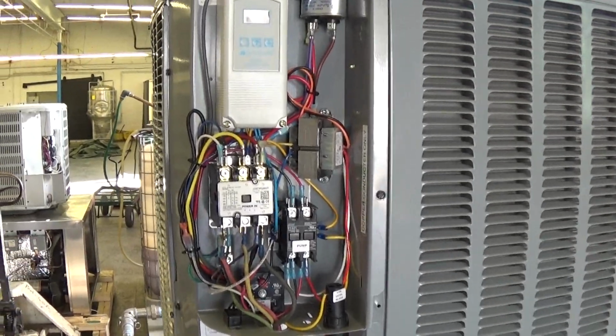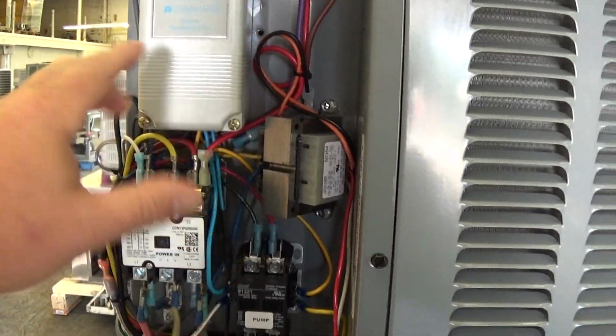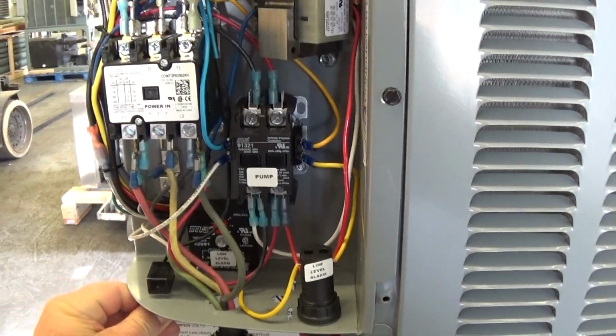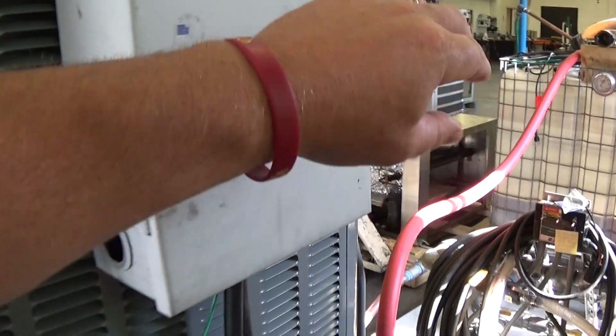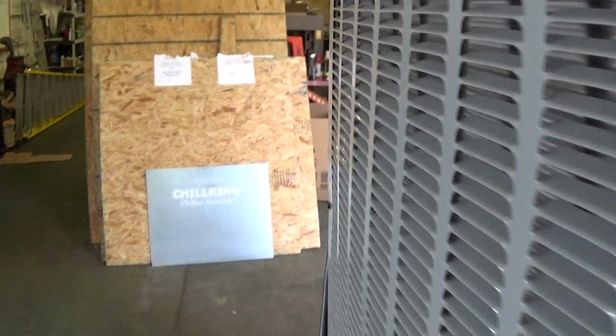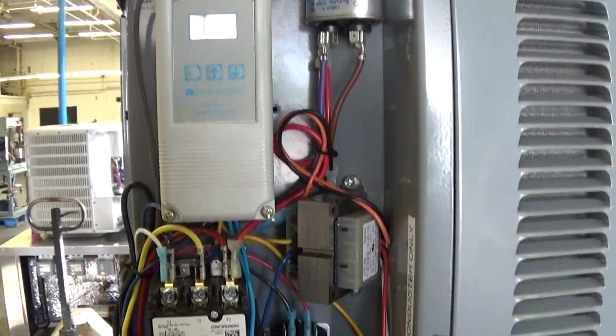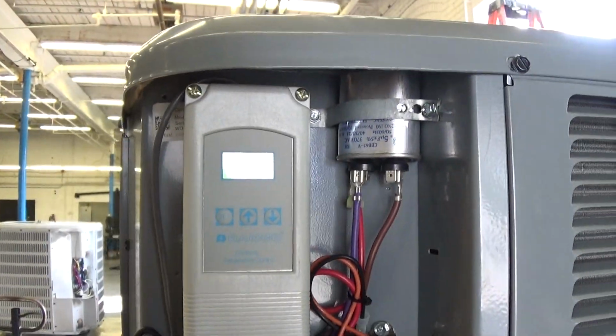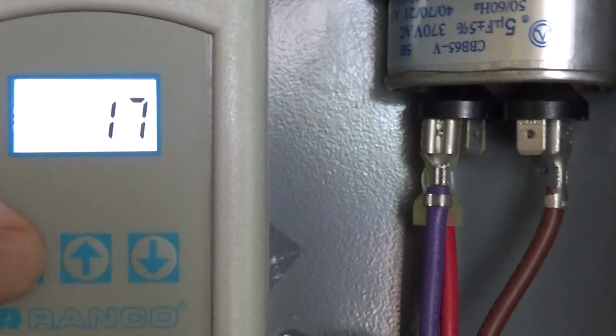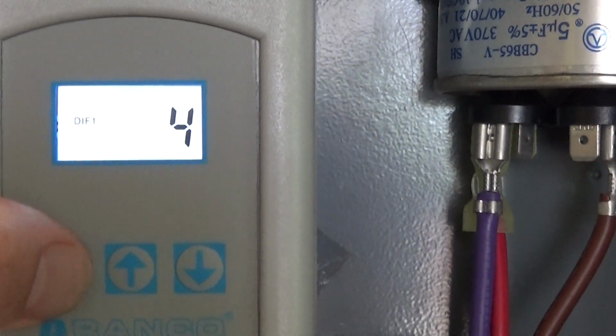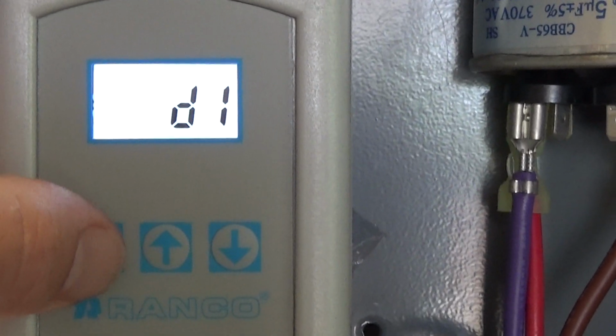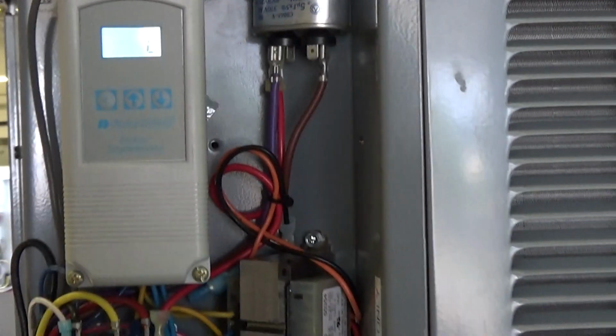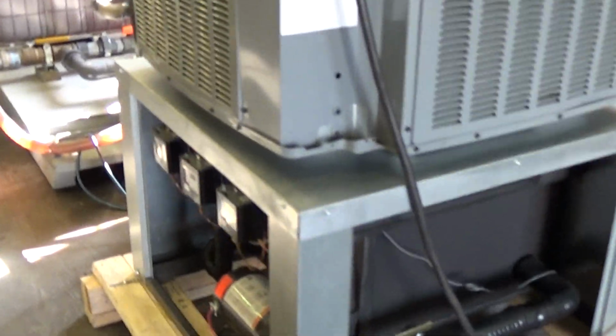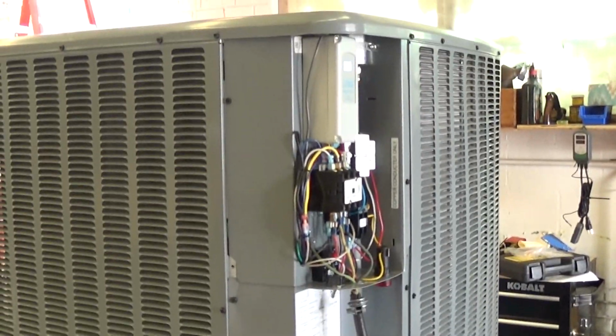So in this example here, we have a Ranco controller. Actually, we're going to power that up right now. This chiller right here we have also programmed in centigrade. Let's see if we can get a good view. Right now the chiller we have set, for example, at 16 degrees Celsius with a differential of 4. And you want a big differential on a chiller. You want to get away with the biggest differential that you can, otherwise the chiller will be short cycling itself. So I'm going to come back with video number 2 here in a second as we turn some things on.